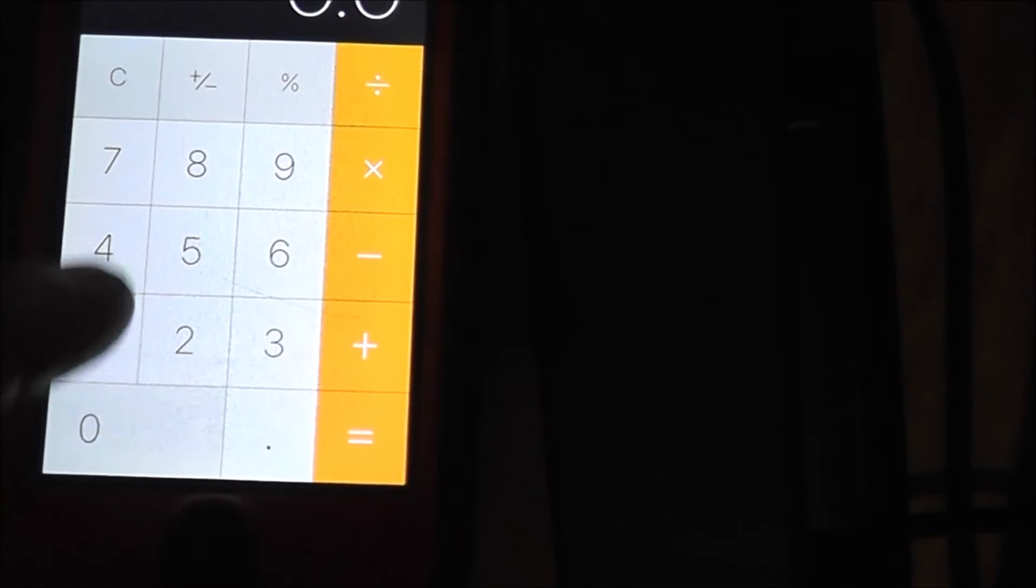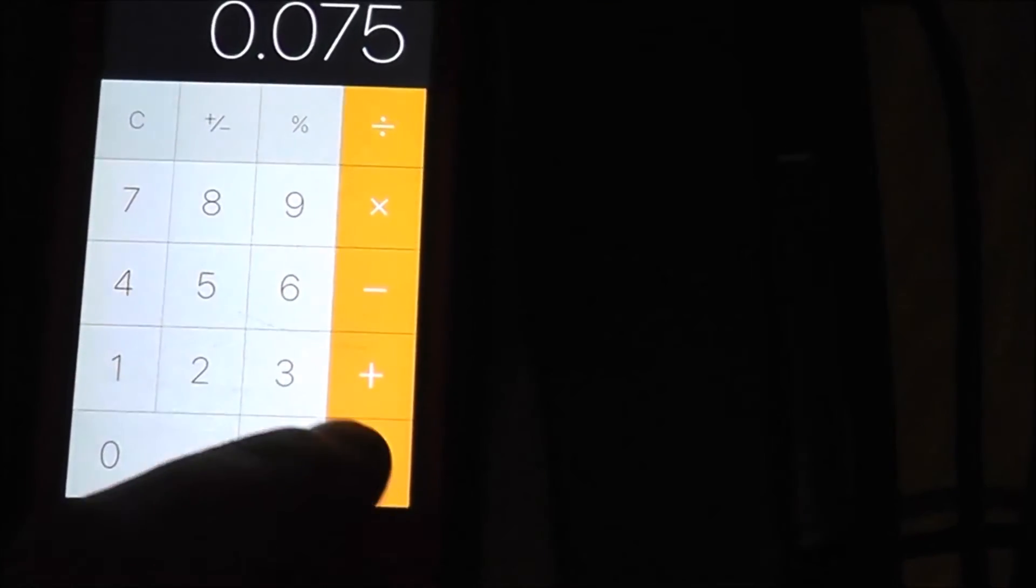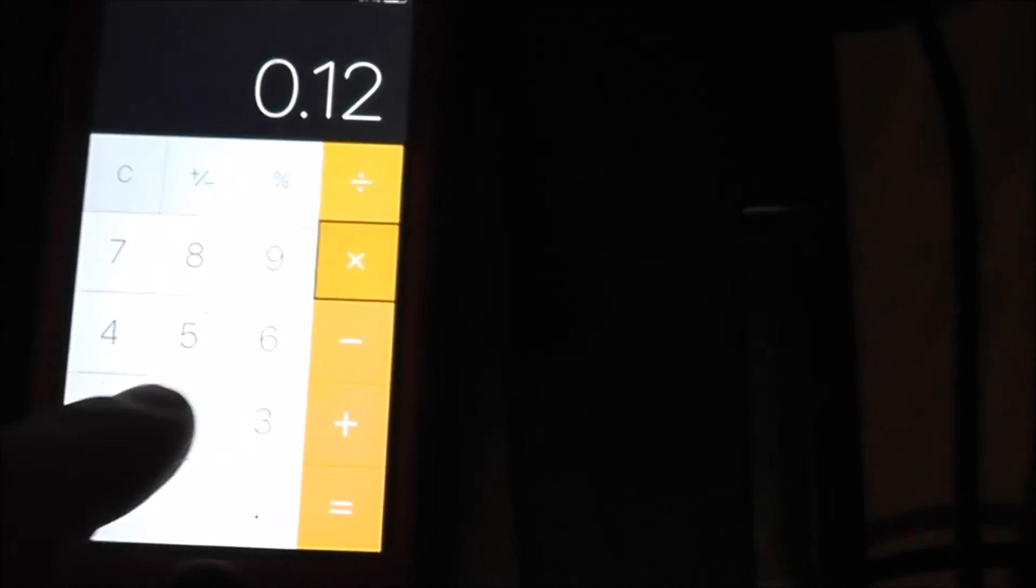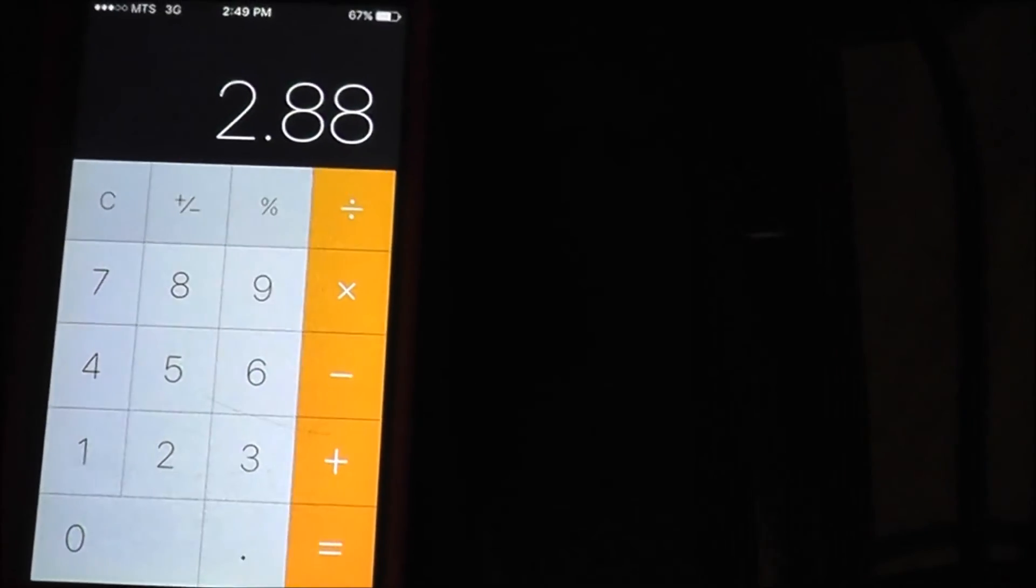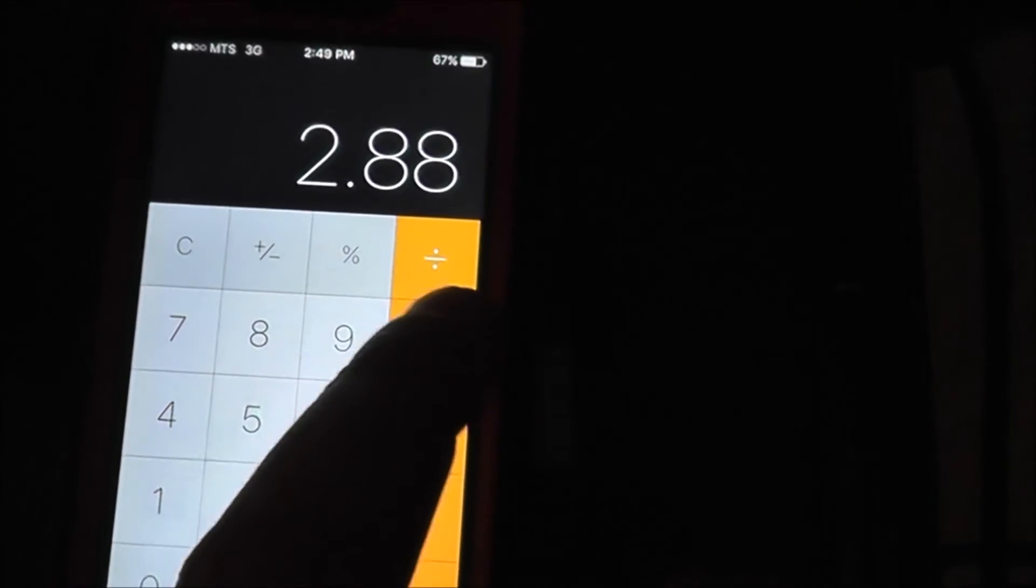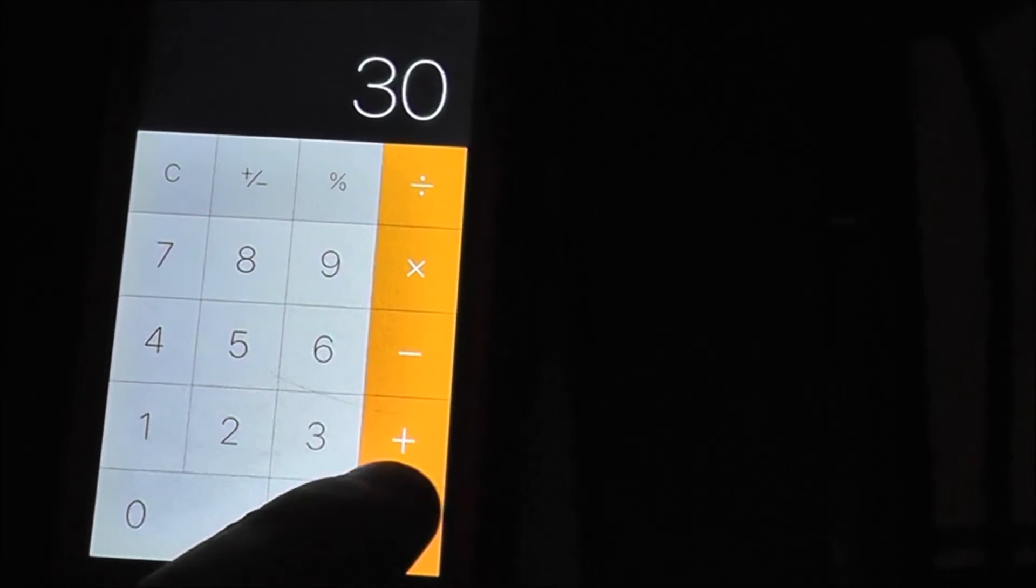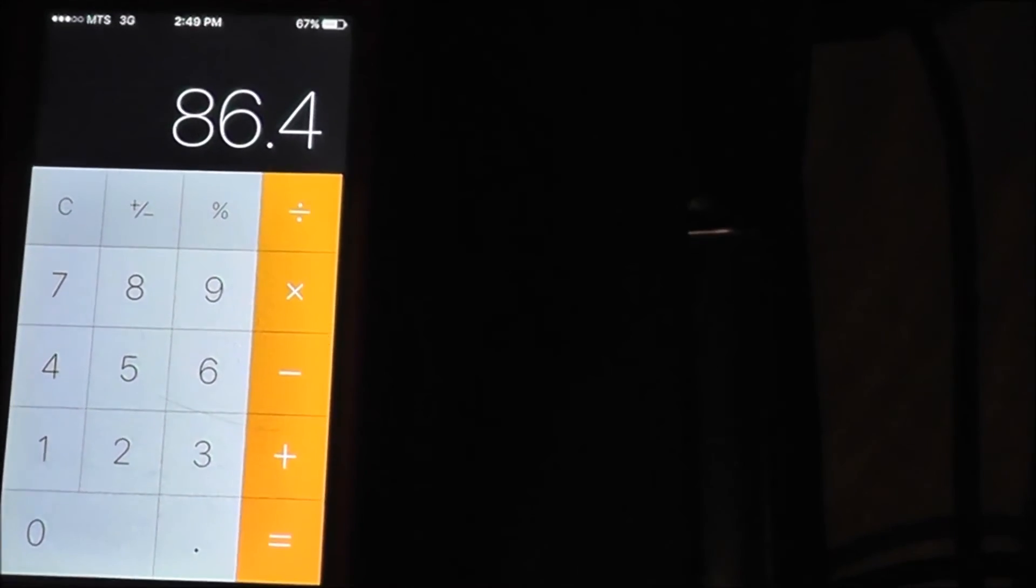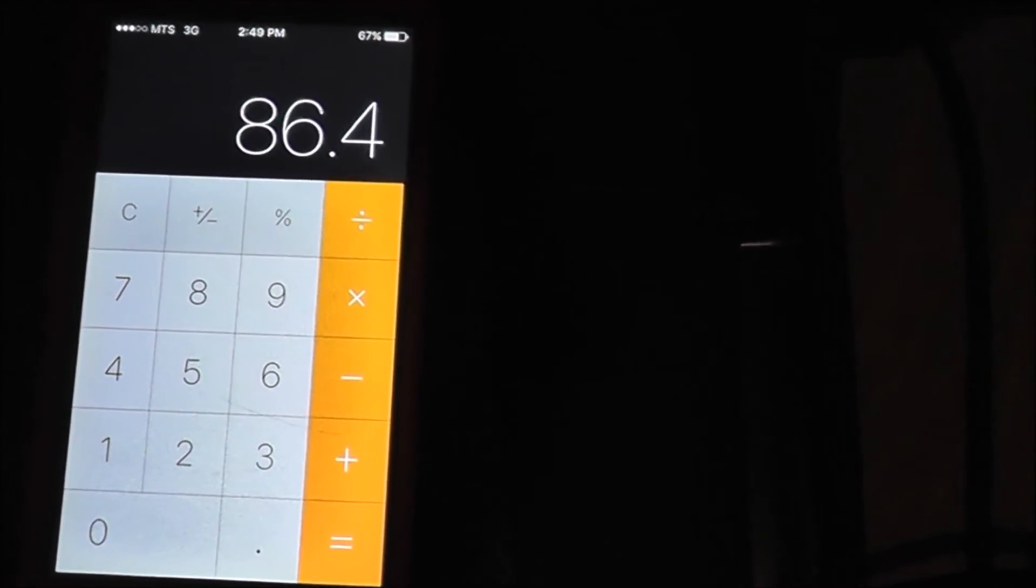Multiply that by 7.5 cents per kilowatt hour, that's 12 cents per hour times 24 hours a day, $2.88 a day times 30 days. So it's $86 a month to run this pump.